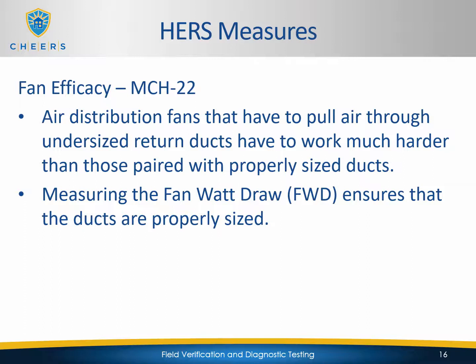So oftentimes these return ducts are either going to be sized too small for the amount of air that they need to move, or they're going to be too long, or they've got too many bends in them. Whatever it is, it's going to create high static pressures, which indicates that the fan's going to have to work really hard to suck that air through.